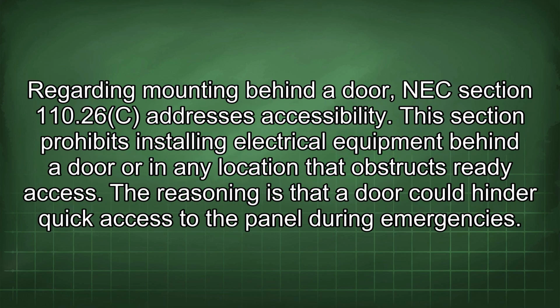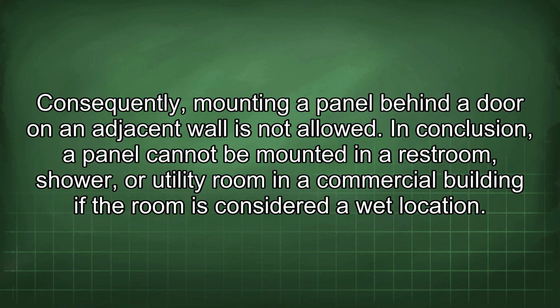Regarding mounting behind a door, NEC Section 110.26(c) addresses accessibility. This section prohibits installing electrical equipment behind a door or in any location that obstructs ready access. The reasoning is that a door could hinder quick access to the panel during emergencies. Consequently, mounting a panel behind a door on an adjacent wall is not allowed.